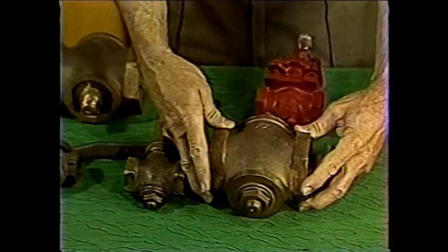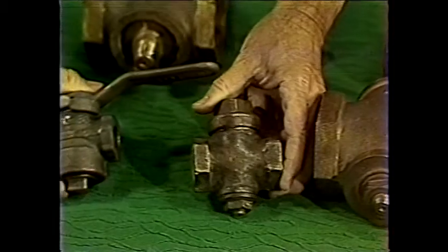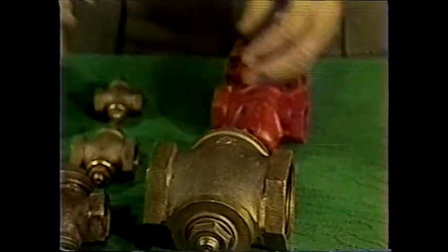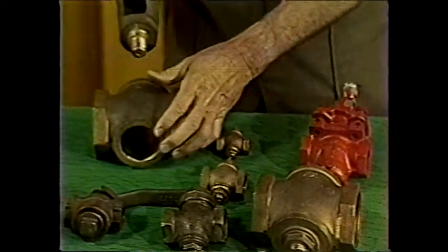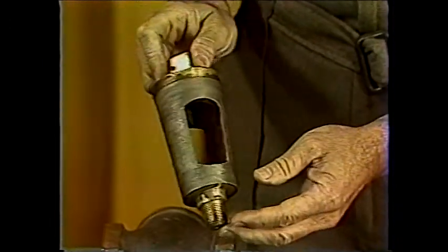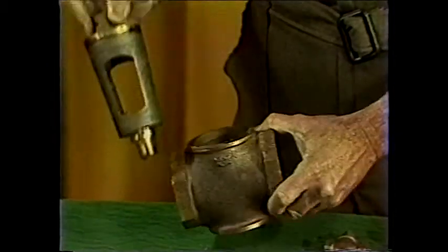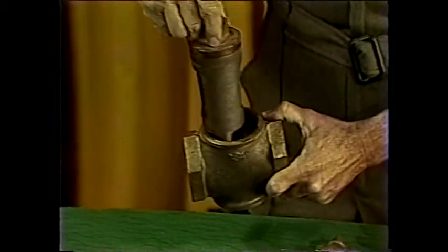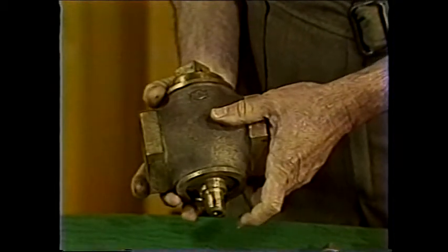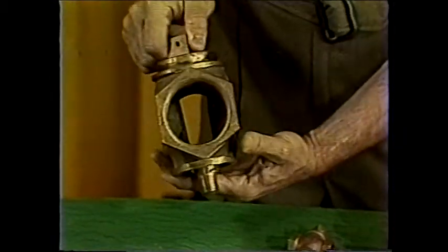First, there's the plug valve. One of the first recorded uses of this type valve was by the ancient Romans in their water distribution systems. Plug valves may have any one of several different designs, but they are all basically the same in that they have a round plug with a hole through it, like this. The hole is usually oval or rectangular and with rounded corners. This plug is then inserted in a round hole in the body, which fits it closely. The plug may be either tapered like this, or it may be straight. The body, of course, corresponds to the plug and also has a hole at either side.